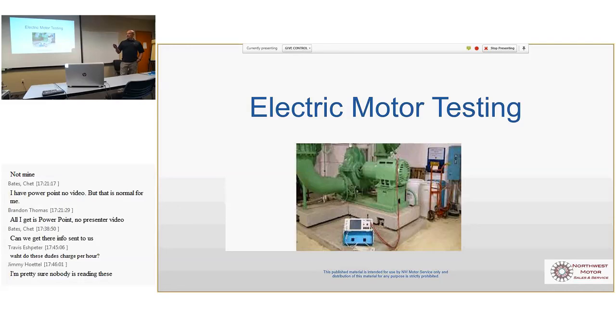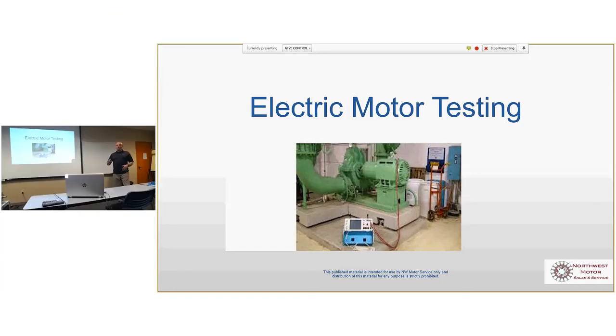So if you have a customer that cares more about their equipment than just running to failure, and they want to do some predictive maintenance, then this is another reason to use this kind of test equipment or have us come and help you. I do a lot of routine testing for people on their critical motors, because this does the lead-to-lead resistance test with a Kelvin bridge, so it gets down to really accurate resistance readings. Just that first test alone, I can tell if the winding is not balanced, that there's probably going to be a problem there. If you just use your Fluke meter, it's going to say 0.1, for instance, phase to phase. But with a tester like this, it's going to say 0.1235 or something. And all three phases need to be within 3% of each other, otherwise there's a problem.